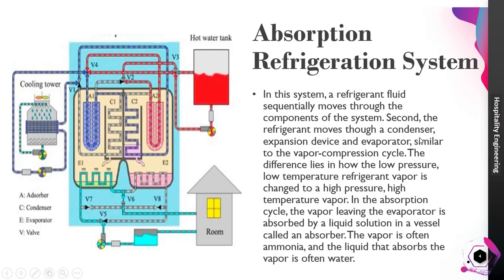The difference lies in how the low-pressure, low-temperature refrigerant vapor is changed to high-pressure, high-temperature vapor. In the absorption cycle, the vapor leaving the evaporator is absorbed by the liquid solution in a vessel called an absorber. The vapor used is ammonia, and the liquid that absorbs the vapor is water. The refrigerant being used is ammonia, and the absorbing liquid is water.